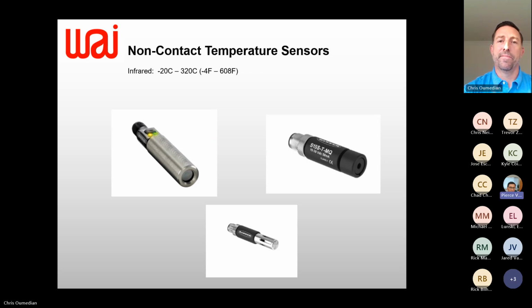I like to use the example of an ice cold Coca-Cola on a summer day. When you step outside, what happens to it? You get water formation on the outside - and water formation on circuit boards and conductive surfaces. This happens along an area Chris and I work in frequently: variable frequency drives, which are blowing up because enclosures aren't designed for avoidance of the dew point.